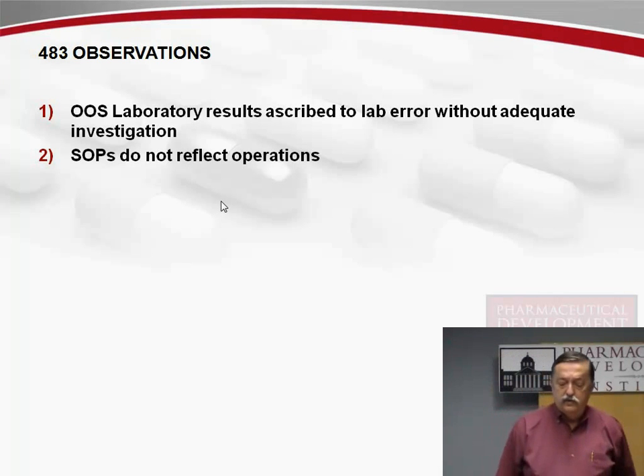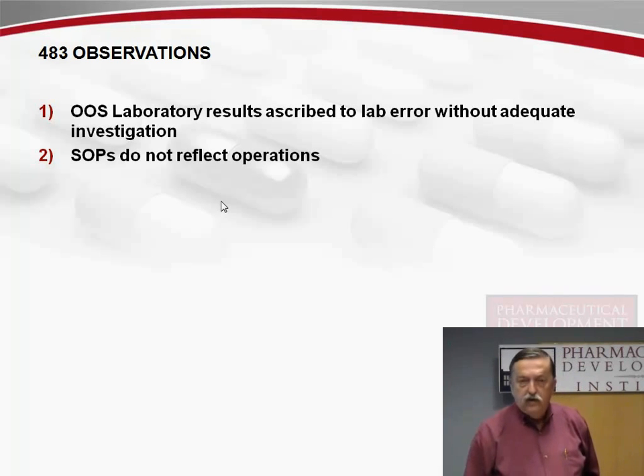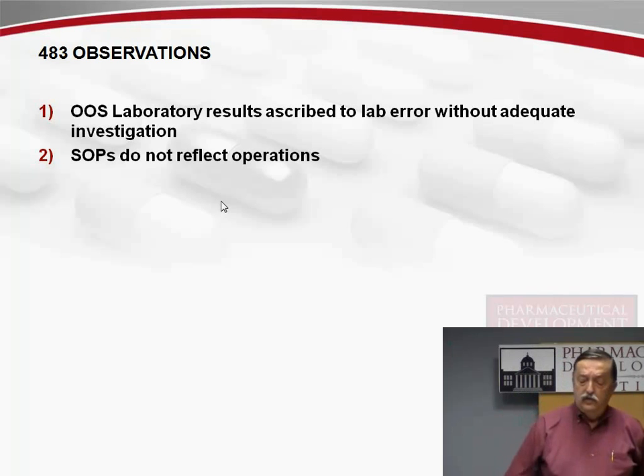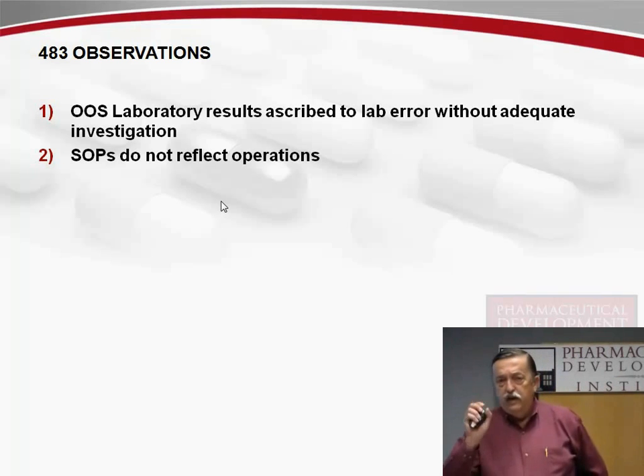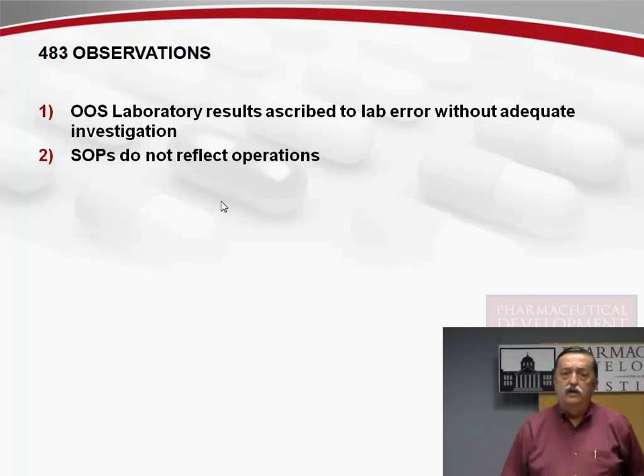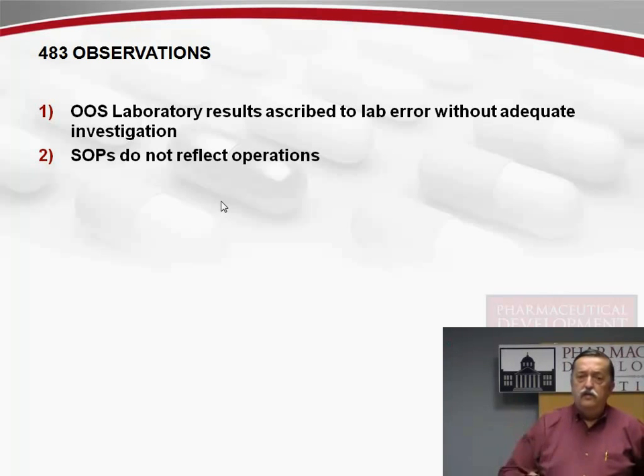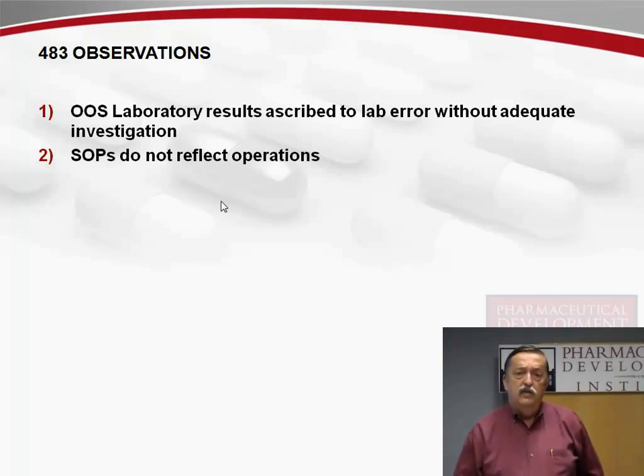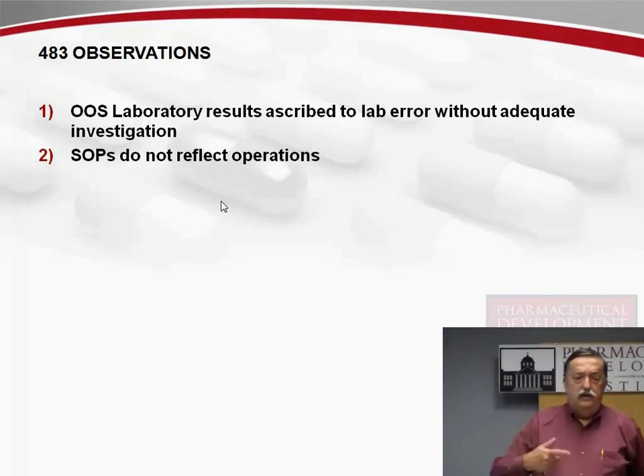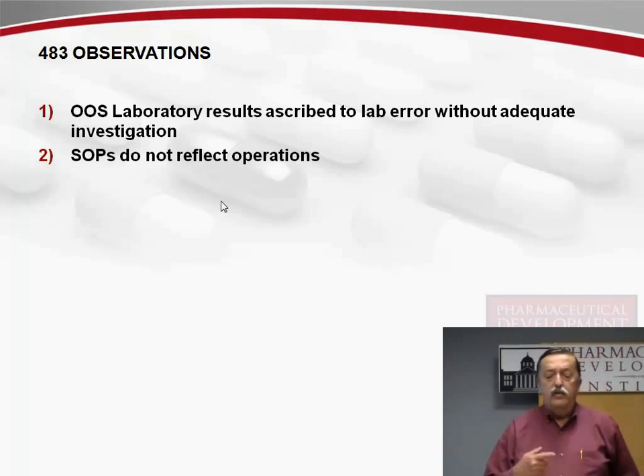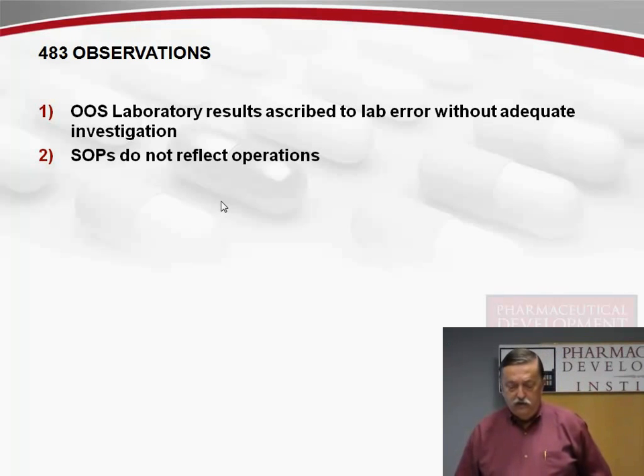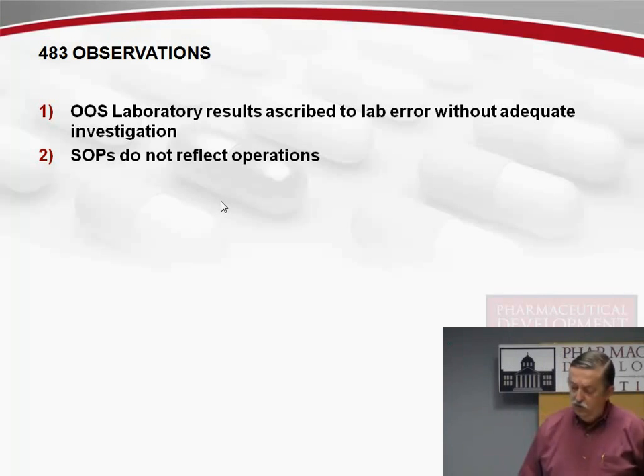SOPs do not reflect operations. Whenever I'm doing an audit, I take a look at the test procedures required by GMP to be in place when the assays and analyses are being performed. If you find any handwritten notes or little yellow sticky notes in them, you know the SOPs do not reflect what's actually being done. The same applies to your manufacturing procedures — if you're constantly having discrepancies because instrument settings or mechanical functions differ, this indicates your SOPs don't accurately reflect operations. This is one of the reasons you want to periodically review your SOPs.